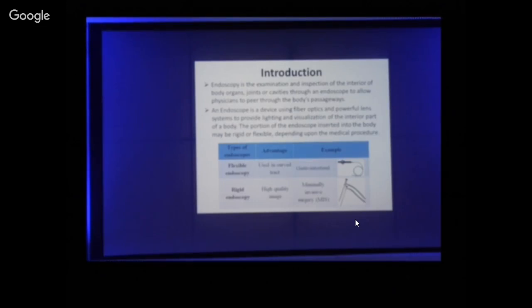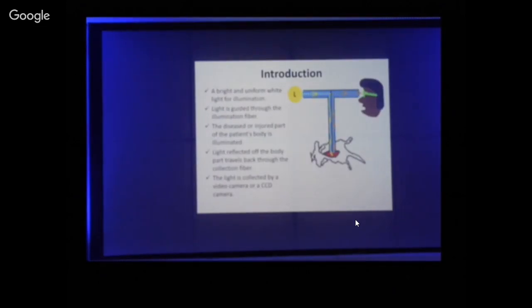Irrespective of the kind of endoscope, whether it is rigid or flexible, it basically uses a light source that is guided to the region of interest and illuminates that region. The image is collected by optical fibers in the tube and directed to an image sensor, like a CCD, CMOS camera or video camera, and so on. The typical diameter of these endoscopes has been reduced a lot nowadays. It's around 2 to 10 millimeters approximately.